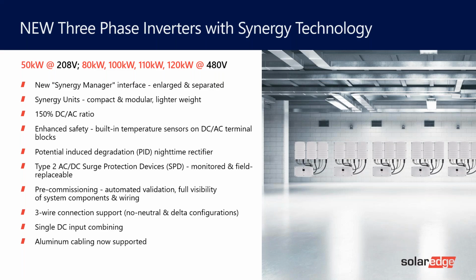The other thing we want to talk about is 3-wire connection support. With our previous Synergy inverter, you had to have 4 wires: the 3 phases, neutral and ground. In this case, you don't need to have a neutral. So it will still work even for sites which we can't control and you can't control. Some buildings don't have the neutral, so in this case you don't need it. It'll still work.